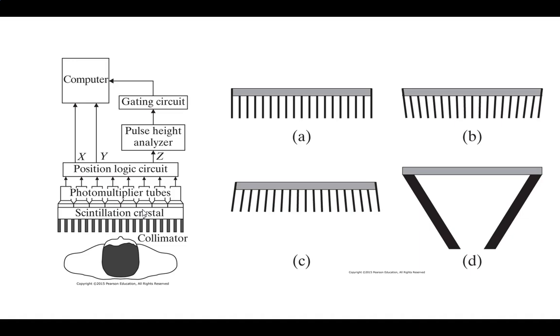And then it's still going to be a weak signal, so we're going to have photomultiplier tubes in different areas, and depending on where it sees it, it's going to amplify it in that particular location. We'll talk about how they do that. That'll give me a strong signal. The tubes will then go into a little digital logic circuit somebody's going to build that says this tube lit up, this was its physical location, and here's its time.